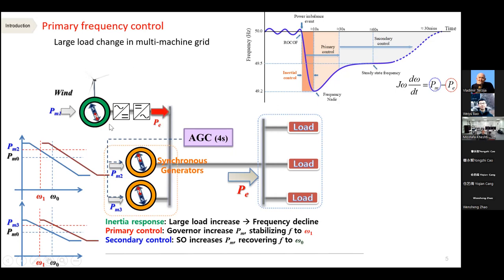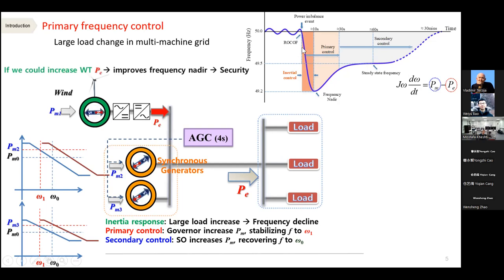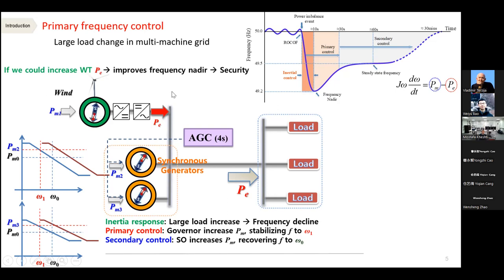Wind turbine generators normally do not participate in such mechanisms because they are working on maximum power point tracking and are isolated from the system through power electronics. Power electronics act as a barrier that prevents the wind turbines from being synchronized to the grid. Our objective is that when a frequency event occurs, we could somehow increase the wind turbine's electrical power output — not mechanical input, because this is wind and we have no control over it. By increasing the electrical power output of wind turbines during a frequency event, we can greatly improve the frequency nadir. Note that AGC is not activated in the UK power system — they use the old-fashioned way of calling power plants to increase their output.